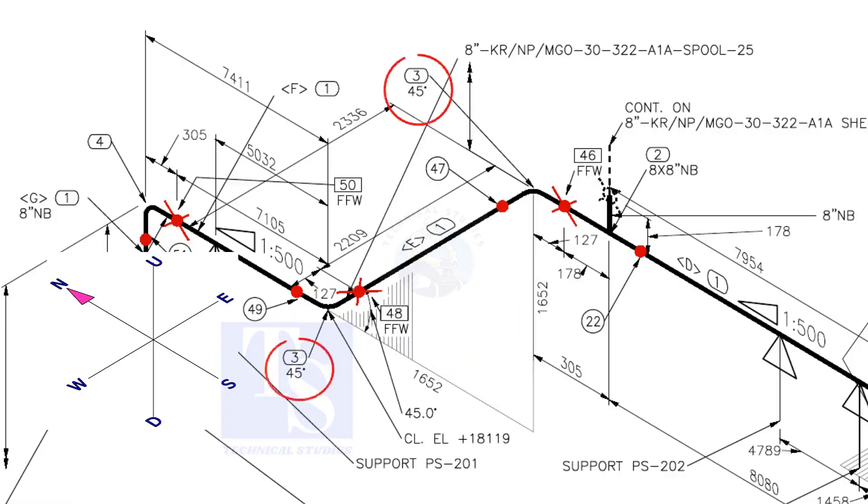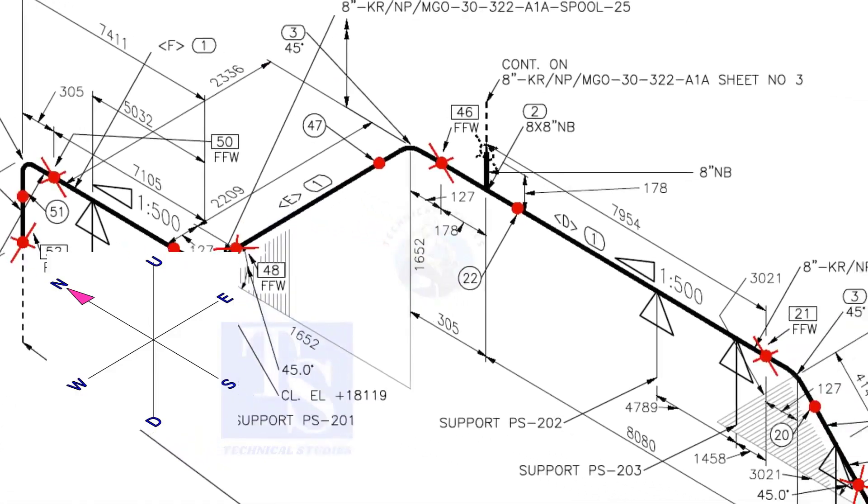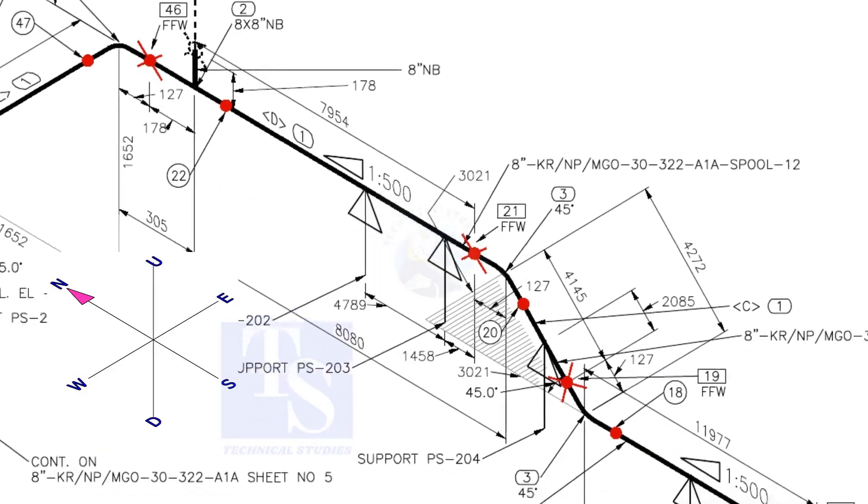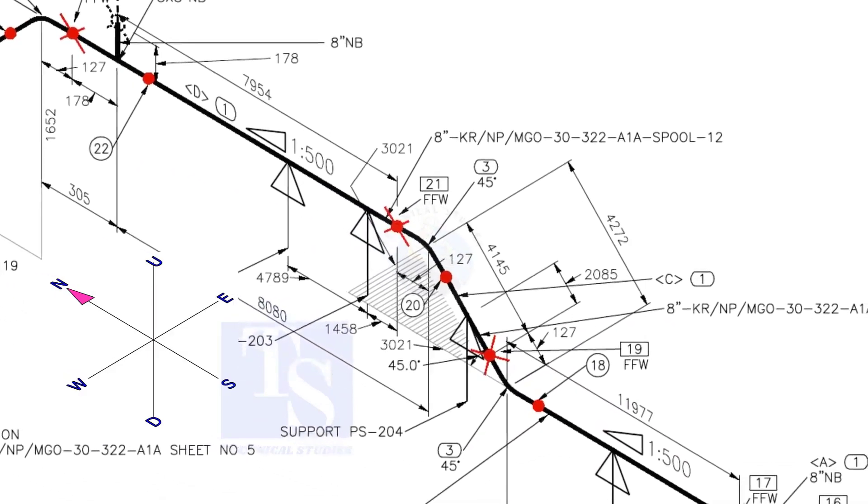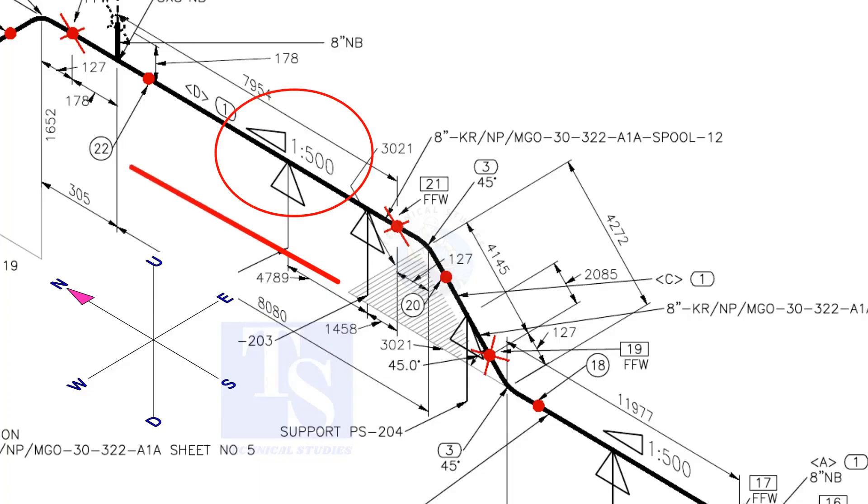Check the rolling degree. Both these elbows are 45-degree. What is this triangle 1 is to 500 mean? It means the pipe is sloping towards the north by 1 millimeter in every 500 millimeters length.